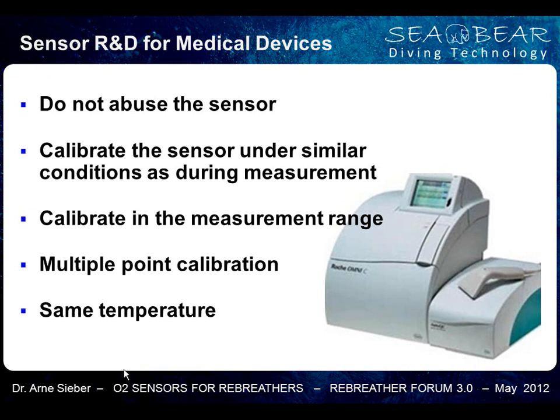And one very important point, which is not written here, but it's very important. If you look at these systems, yes, they calibrate automatically, maybe each 2 hours, each 4 hours. But before and after each measurement, they make a sensor validation. They flush the sensor with a liquid with a certain amount of gases, with a certain amount of ions, and by doing this, they can see if the sensor is working correctly.